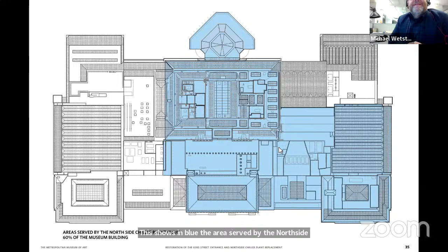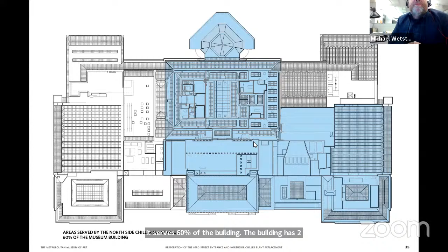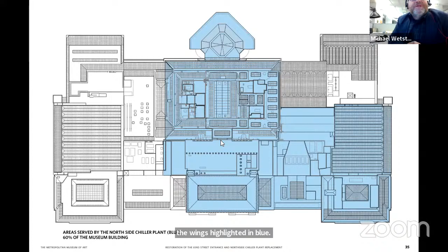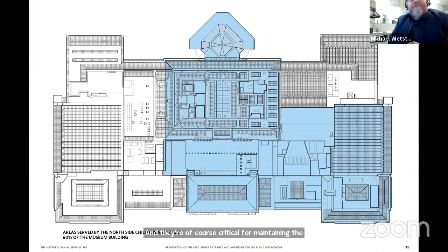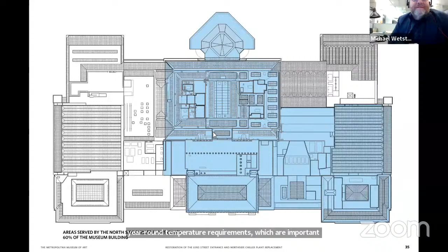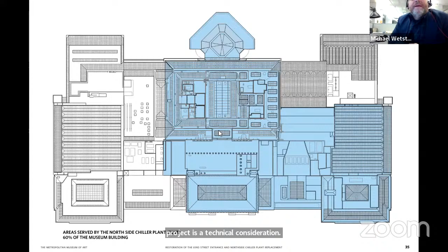This shows in blue the area served by the north side chiller plant. It serves 60% of the building. The building is 2.1 million square feet, so this serves 1.25 million square feet. The chiller plant makes chilled water, which is pumped in pipes to the HVAC systems in all the wings highlighted in blue. They're critical for maintaining the museum's constant 70-degree, 50% humidity, year-round temperature requirements, important for art conservation. Really everything about this project is a technical consideration in support of the art conservation requirements.